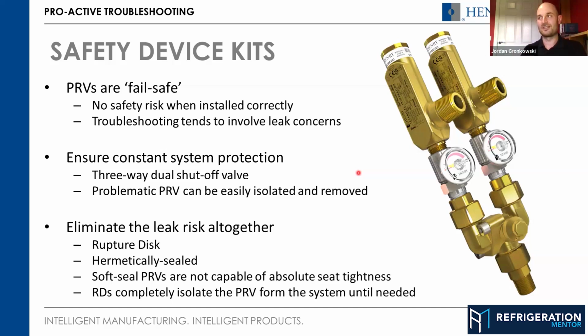It's not designed to. And although it's easy to think, well, the force of air or gas is going to blow this off, it's amazing what that initial moment of back pressure that it sees when it opens can do, and it can force the valve to close again. And then maybe the cap comes off, but the valve's already kind of stuck itself. It's strange because it can actually affect the set point as well, which is almost counterintuitive. You think it opens and closes, but it kind of closes with such force that it bites into the seat more, and it can actually make the valve set higher. Wow, it's really strange. See, I didn't know that.